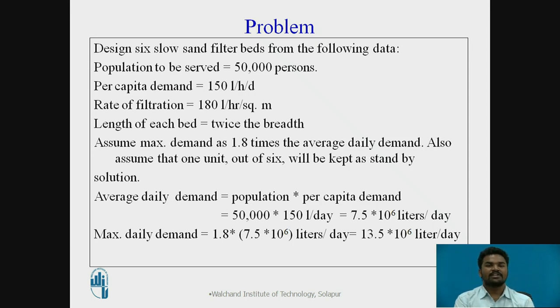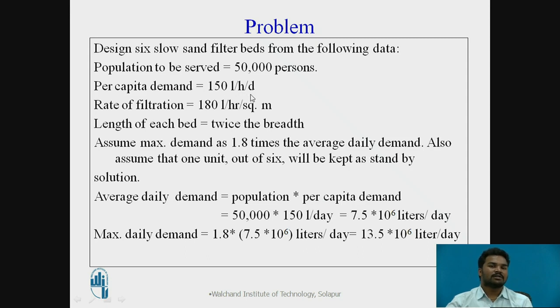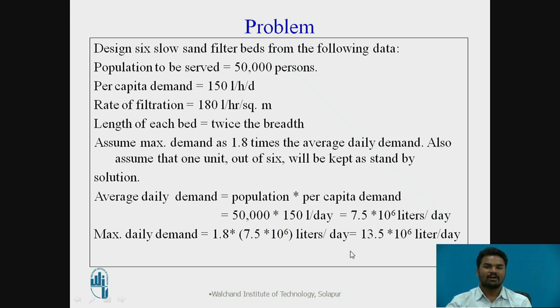Solution: Average daily demand = population × per capita demand. Per capita demand means each person requires 150 liters of water per day. So average daily demand = 50,000 × 150 = 7.5 × 10⁶ liters per day. Maximum daily demand = 1.8 × 7.5 × 10⁶ = 13.5 × 10⁶ liters per day.